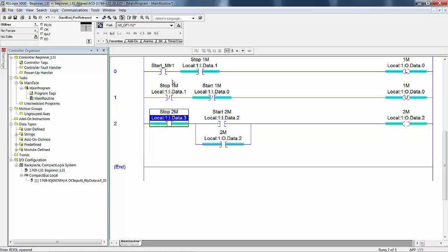On the other hand, the scope of the tag is what you need to be thinking about when you define the tag. The controller tag database was last selected, and this pop-up came up with your last choice. If you were to select create without changing the scope, the tag would have been created in the controller tags database and not in the program tags database where we want it.